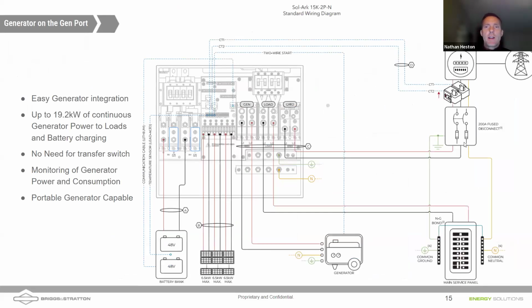Here are some wiring diagrams out of a Sol-Ark 15k manual, and we're showing the generator coming into the gen input. So, a lot of questions. Can we integrate a generator? Is it easy to do? Sure, it does need to be 240 volts. If you have a two-wire signal to start, that's preferred, because then the inverter can start and stop the generator only when it needs to, when batteries get low.